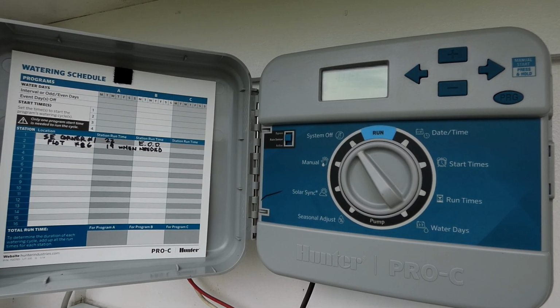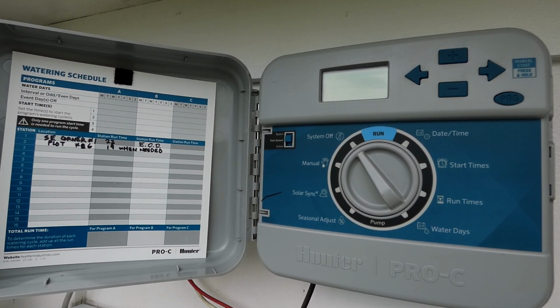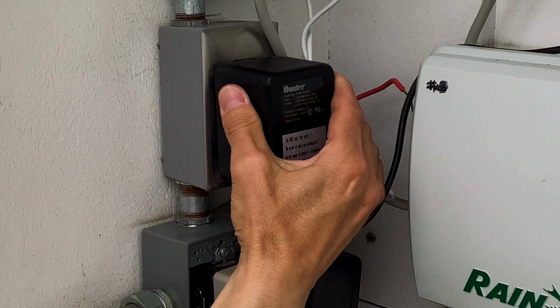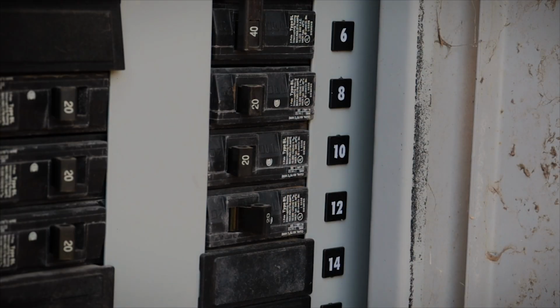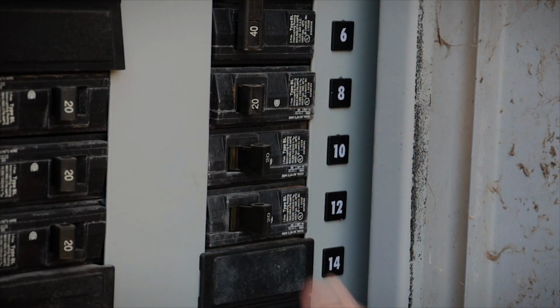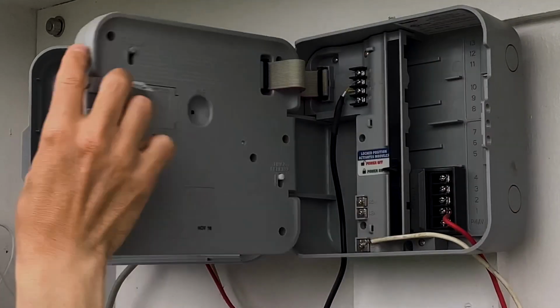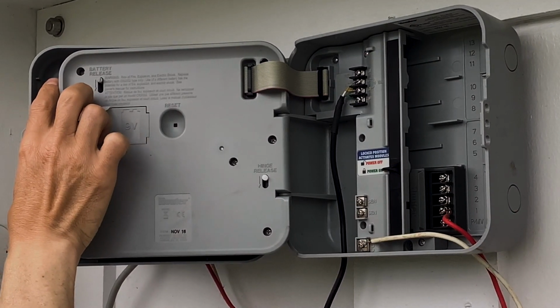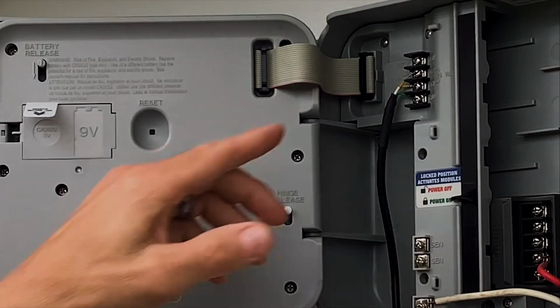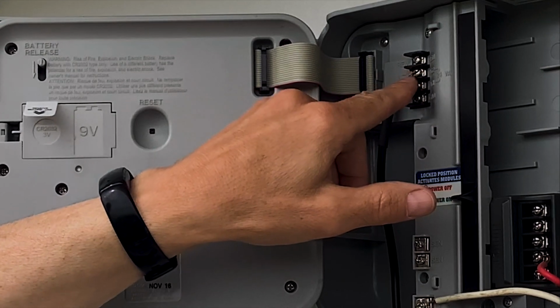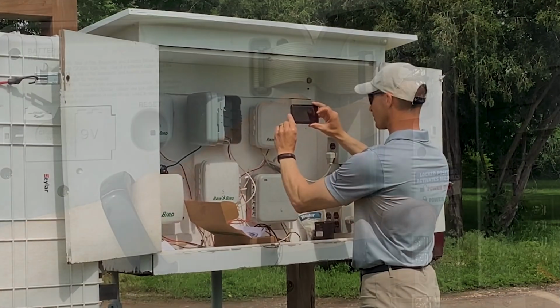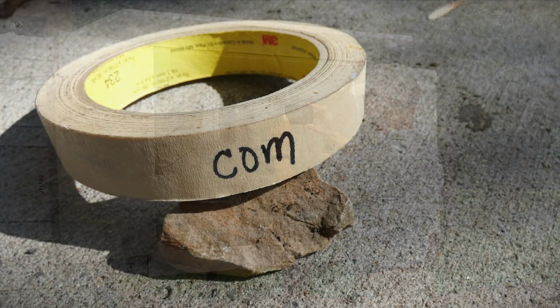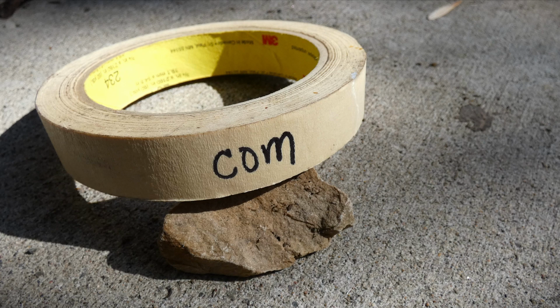Before you begin, disconnect the power to your existing controller. If it's plugged into an outlet, unplug it, and if it's hardwired, turn off the circuit breaker. Open your existing controller to access the wiring terminals. You'll want to remember which zone or function each wire corresponds to. Do this by taking a before photo or labeling each wire with masking tape.